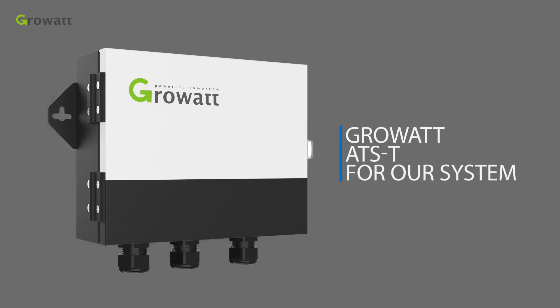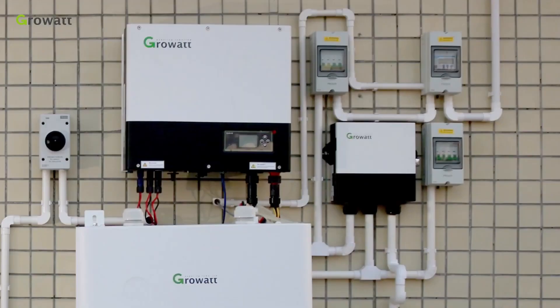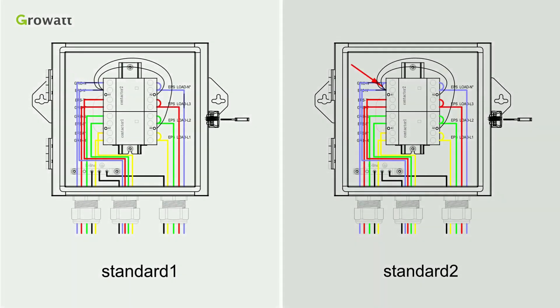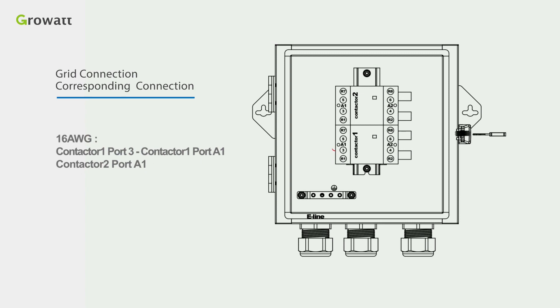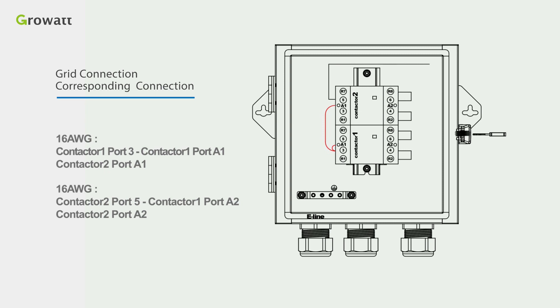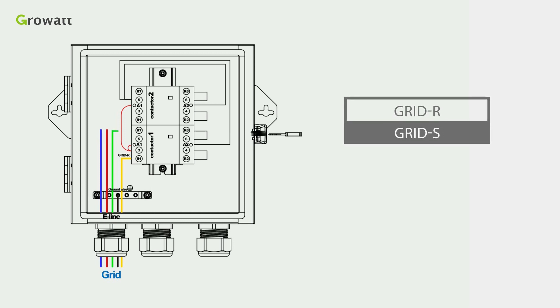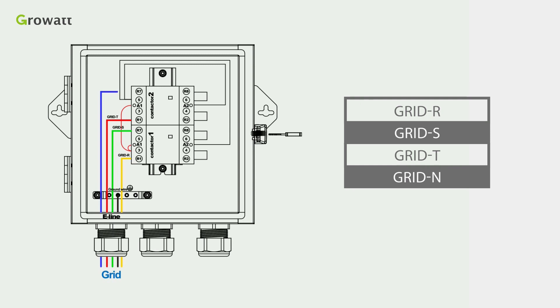If the customer requires a backup power function, Growatt provides the optional ATS-T for the system. Follow the diagram to connect the ATS-T. Standard 1 is for general use and Standard 2 is for markets like Australia where the neutral line cannot be switched. Use 16 AWG cable to connect contactor 1 port 3 to contactor 1 port A1 and contactor 2 port A1. Use another 16 AWG cable to connect contactor 2 port 5 to contactor 1 port A2 and contactor 2 port A2. Then connect 10 AWG cable of grid R, grid S, grid T, and grid N into the corresponding ports as illustrated, and lock the ground cable on the copper bar.